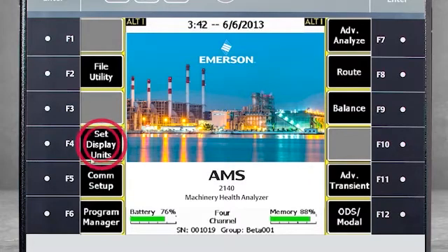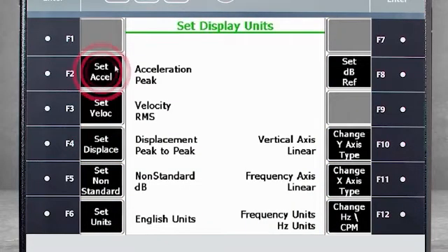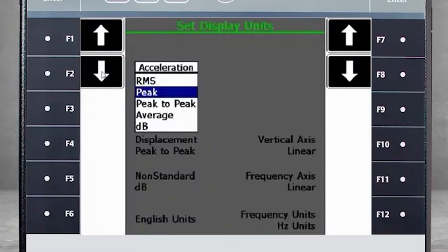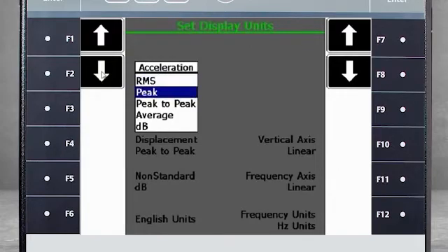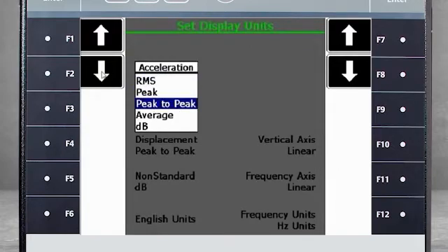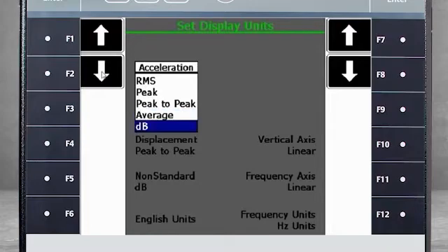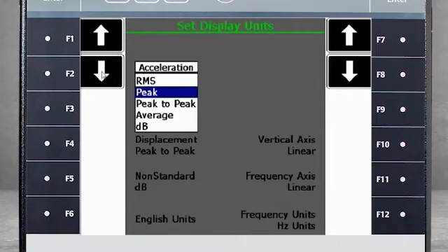F4 Set Display Units. From this screen, use F2 to specify how you want to see the acceleration signal. Note that changing the display units here will change the display for all previously collected data in the analyzer. For example, if you select Peak and go back to look at previously collected data, it will be displayed in Peak. If you want to see that data again in RMS, you simply come back to this screen and select RMS.